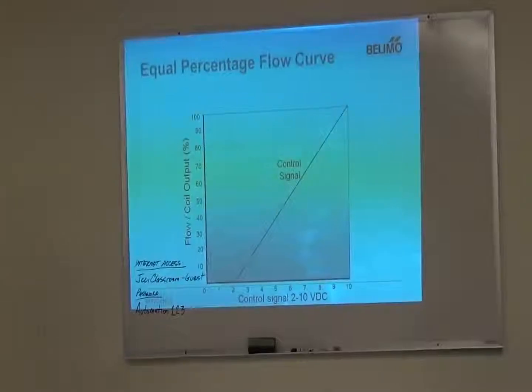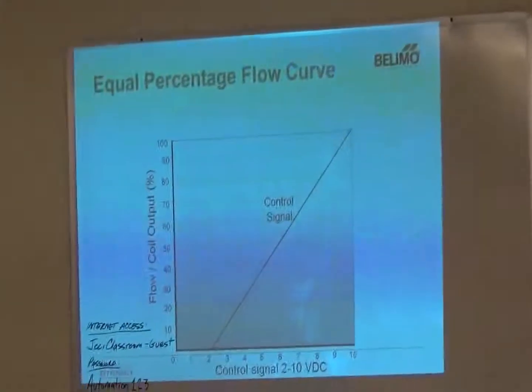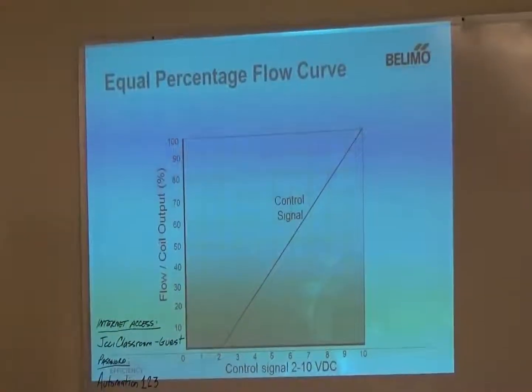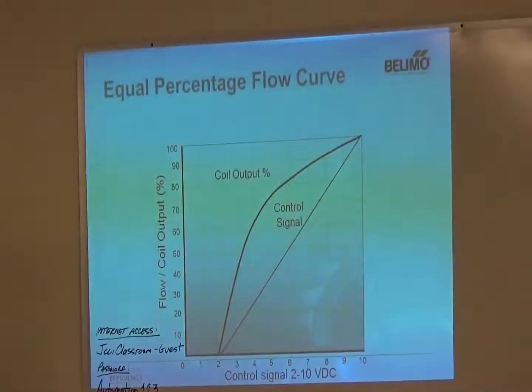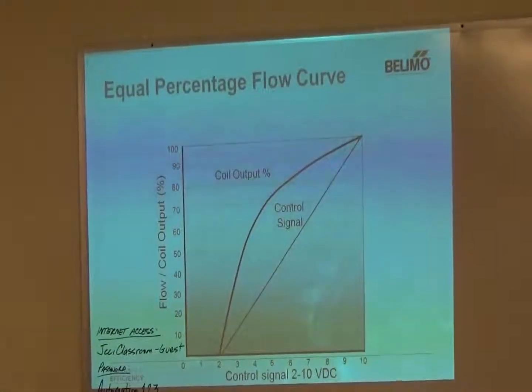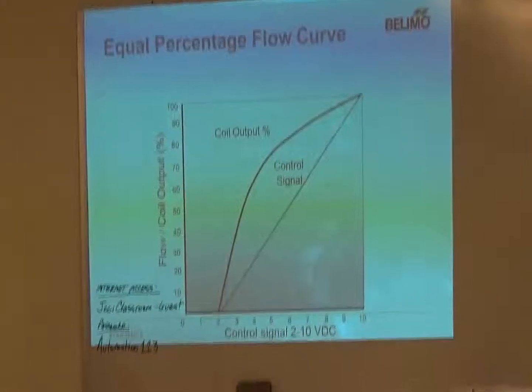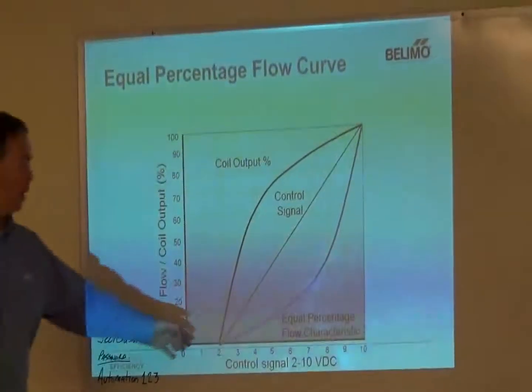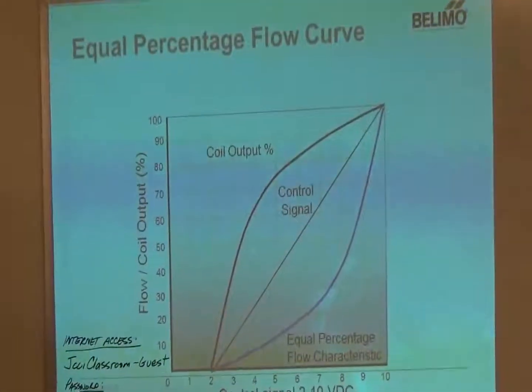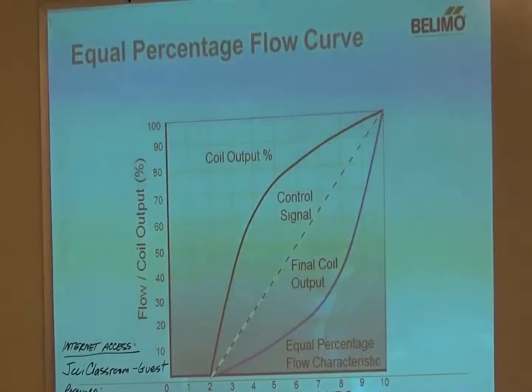So this is just a graphic showing a 2 to 10 volt control signal. And you're probably guessing what I'm getting to here. You've probably all seen it before, that nice little football-shaped graphic. But what we're looking at is our coil output curve. Then, as we've probably all seen in the past, we want an equal percentage flow characteristic out of our valve so that our final coil output is linear. So what that means is, at half our signal, we're going to be getting half of our coil output.